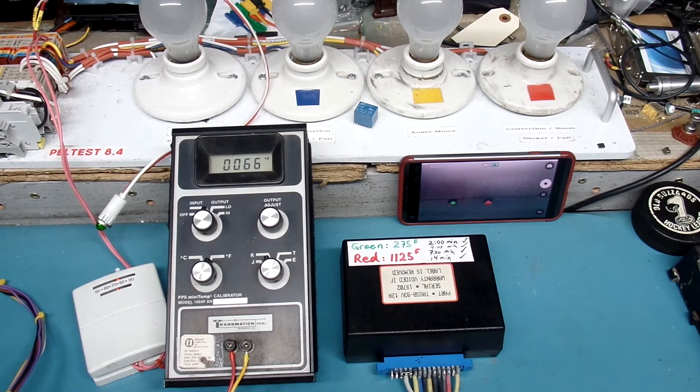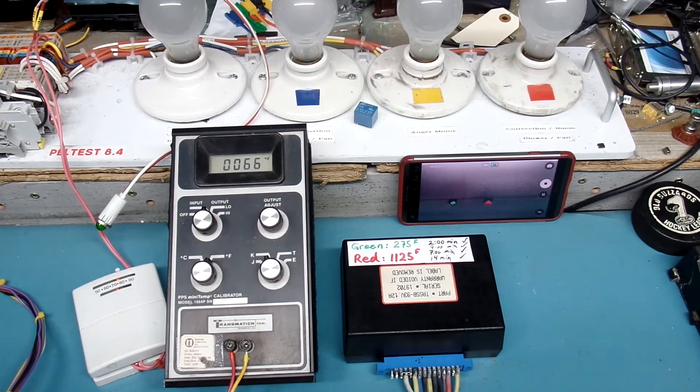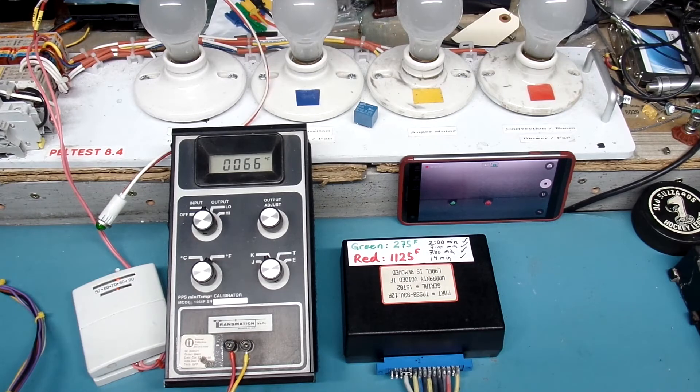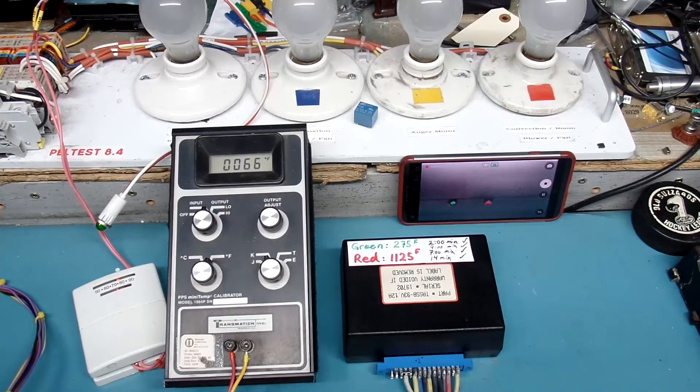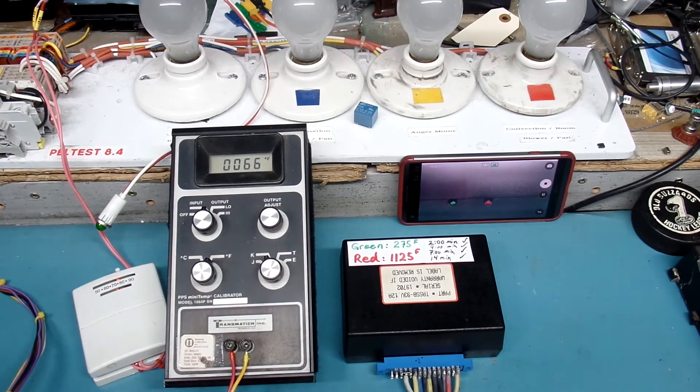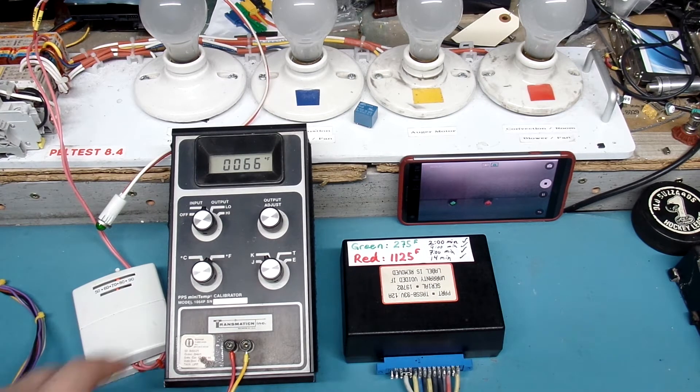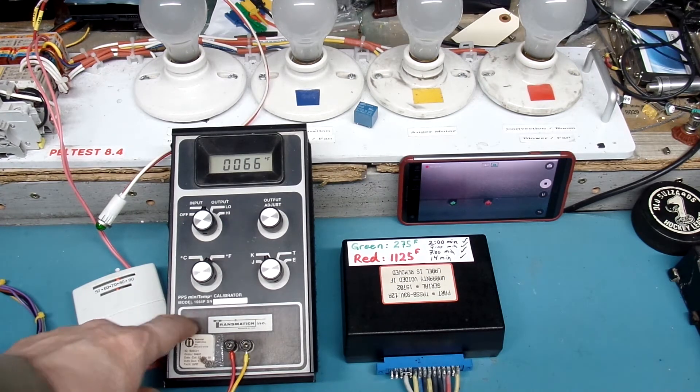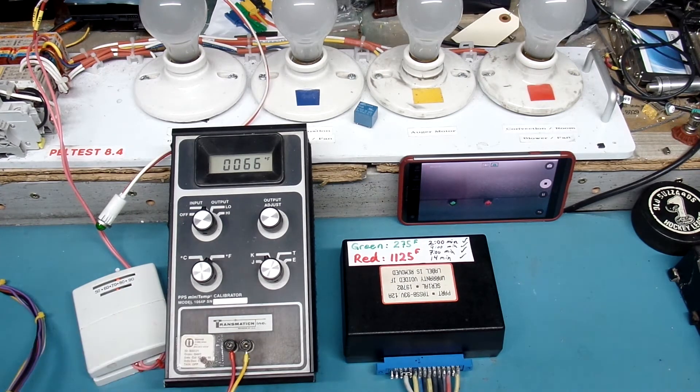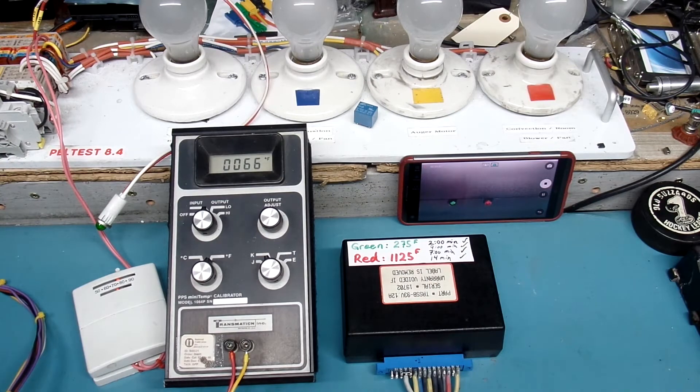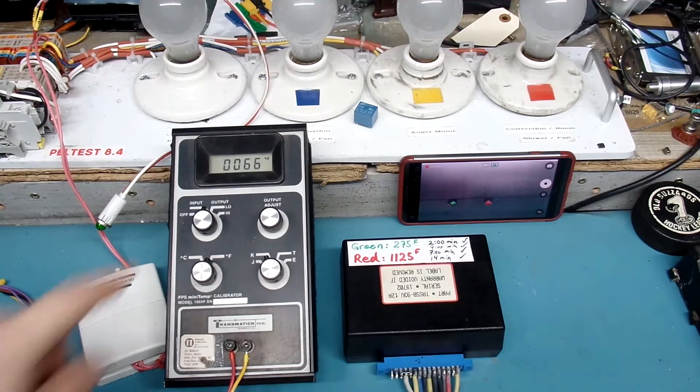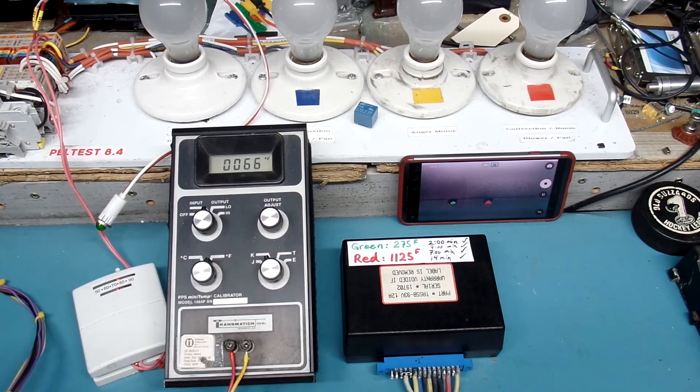So it's time to do the final test before returning it to Jeff. I currently have the controller connected to my tester. I use a wiring harness to do that. It also connects it to a temperature simulator which simulates a K-type thermocouple. As you can see, I have it set to 66 degrees Fahrenheit.